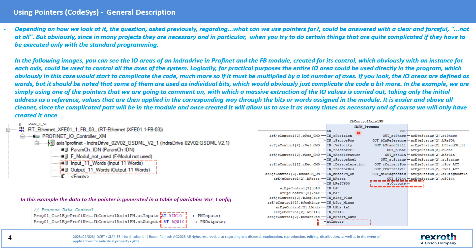It is evident that we can put all the words directly in the PLC program. It must be taken into account that some of the words are part of values that come and go in double-integer format. Some of the words must be modified by means of factor values to adjust the number of decimal places that IndraDrive must receive and send. In addition, some of them will be used in the form of individual bits to activate movements or retrieve the status of the IndraDrive.